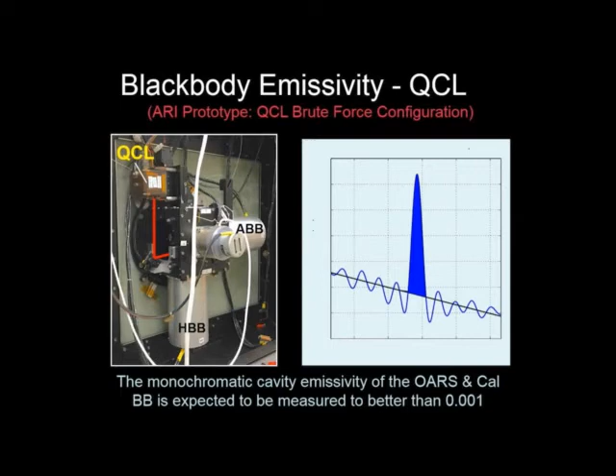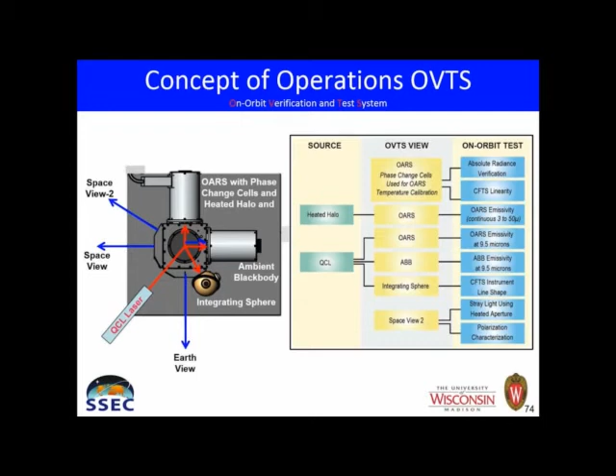And so all the different measurements that we can make: absolute radiance verification with the OARS. We can check calibrated FTS linearity. We can measure spectral emissivity from 3 to 50 microns. We can do this monochromatic emissivity with the QCL and make that measurement of our ambient black body. We can do the instrument line shape. We also have a way to look at stray light issues by putting heated apertures wherever our beam looks outside the instrument. And that'll give us a signal to tell us that, hey, you're viewing something you don't want to be viewing, and then the polarization. So you can think of 2 different time scales of how this works, so over 2 minutes, this is a calibration cycle.